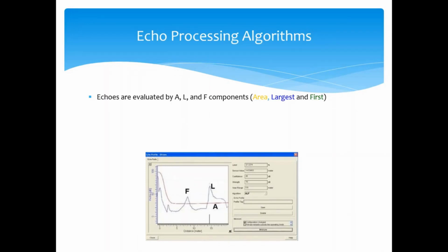So some of those algorithms that I was talking about, there's 3 components that make up the different algorithms that we have. The 3 components are whether the spike or the signal return is the first one to go over the threshold or corresponding second, third, fourth, etc. Then we look at the height, or how large that signal return is above our threshold value. So that's kind of like our amplitude, overall size of the spike. And then we look at the area of the overall signal rising above that threshold value. So some of our algorithms might look specifically at just the first echo. We would use that, for example, in a stilling well application. We know our first echo will always be true liquid level.